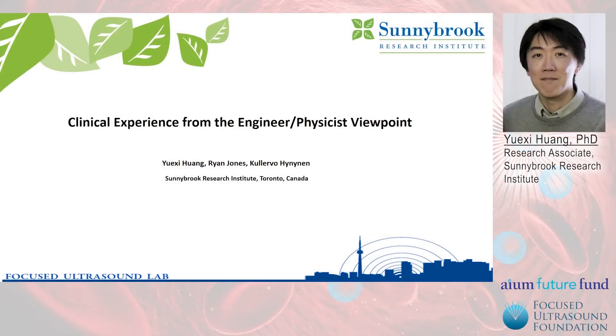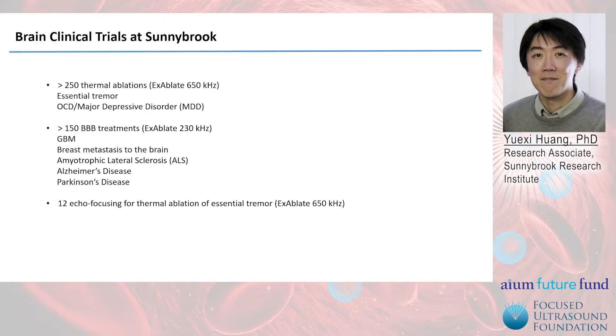Hi, my name is Yuxi Huang. I work at the Kullervo Hynynen's lab at Sunnybrook. In the past 10 years or so I have been working as a physicist in clinical trials, especially with Insightec's brain systems. I'll share some of our experience using these systems from a technical and practical perspective. At Sunnybrook, we have treated over 250 patients on thermal ablations — mostly essential tremor, OCD, and depression. We have also performed over 150 BBB treatments using the 230 system in multiple trials on GBM, breast metastases, ALS, Alzheimer's, and Parkinson's disease. In addition, we have treated 12 tremor patients using echo focusing. Comparing these three applications on cavitation control, echo focusing is currently the most advanced on the engineering level, while BBB is the most challenging because the cavitation level needs to be related to a variety of biological effects.